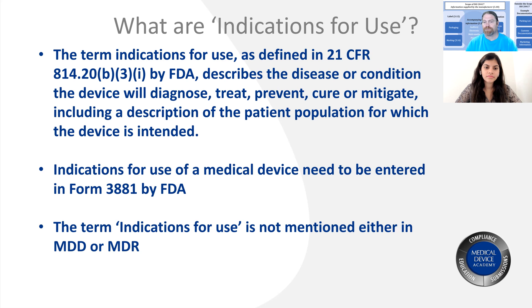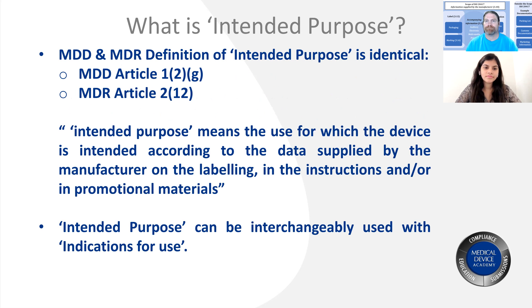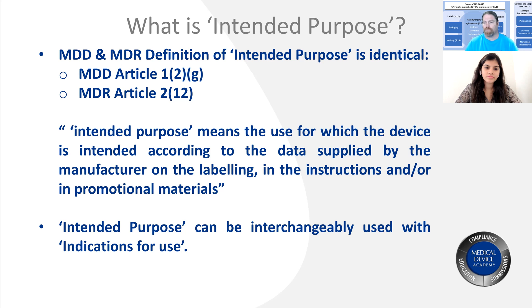Interestingly, the term 'indication for use' is never used in the MDD or the MDR. Instead, they use the term 'intended purpose.' In both the MDD and the MDR, the definition is identical — it hasn't changed between the old directives and the new regulations. So intended purpose can be used interchangeably with indication for use. It doesn't matter which one you use in your labeling, but 99% of labels, instructions for use, or device descriptions out there use the words 'indication for use.' It means the same thing as intended purpose in this context.